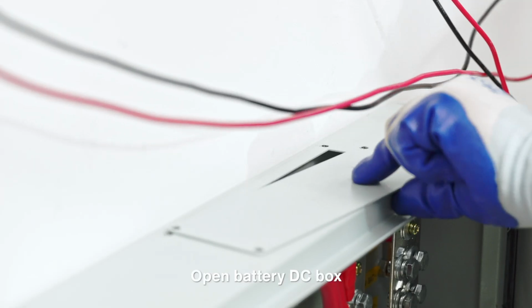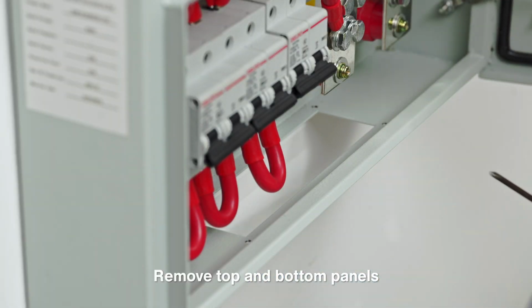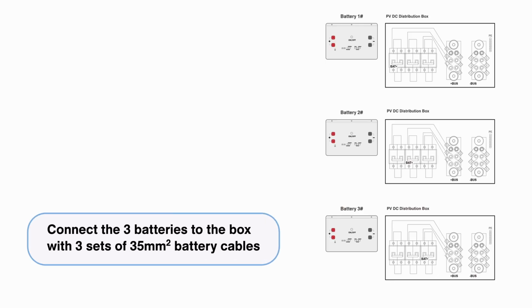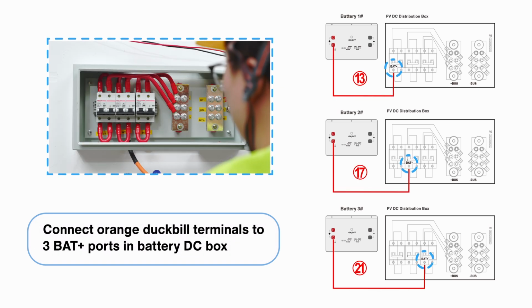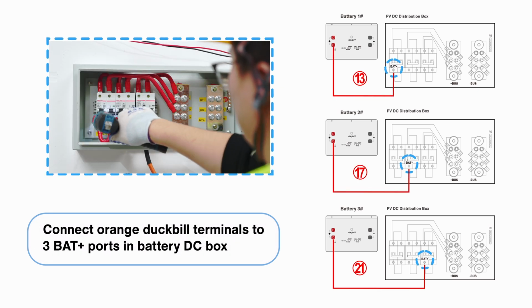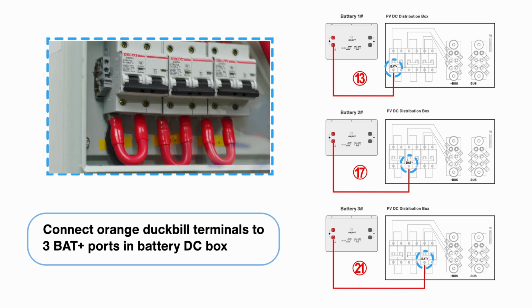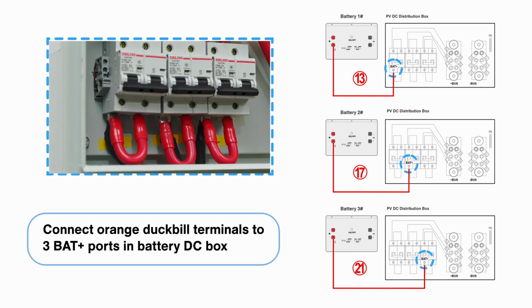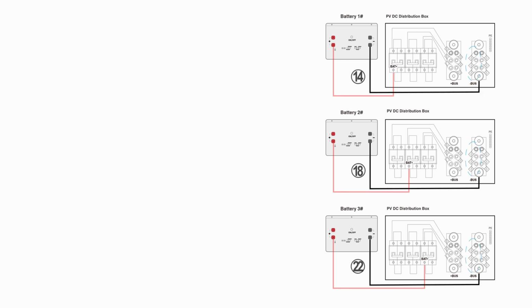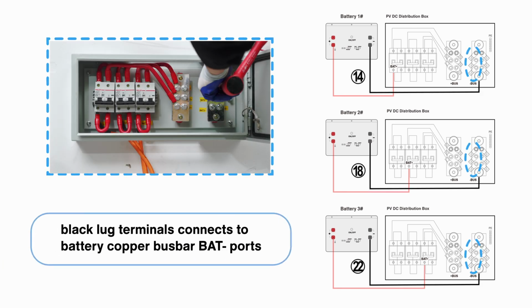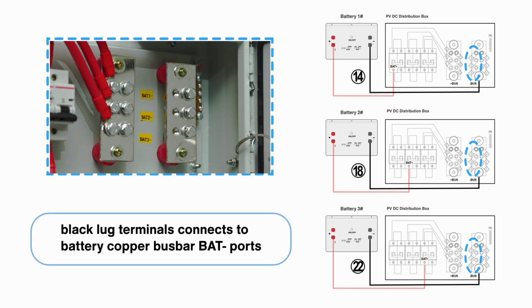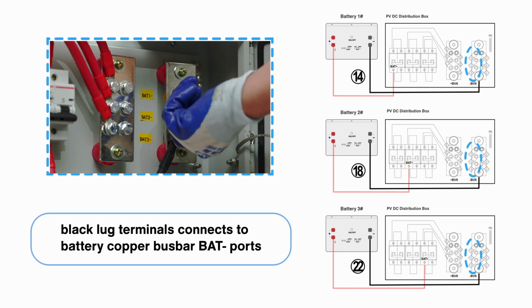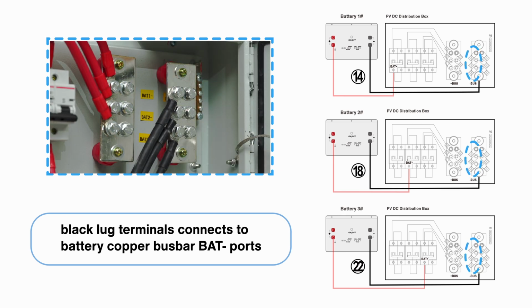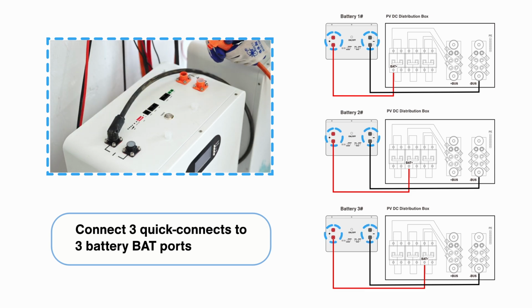Battery cable connection. Open battery DC box. Remove top and bottom panels. Connect the 3 batteries to the box with 3 sets of 35 mm squared battery cables. Connect orange duckbill terminals to 3 BAT plus ports in battery DC box. Black lug terminals connects to battery copper busbar BAT minus ports. Connect 3 quick connects to 3 battery BAT ports.